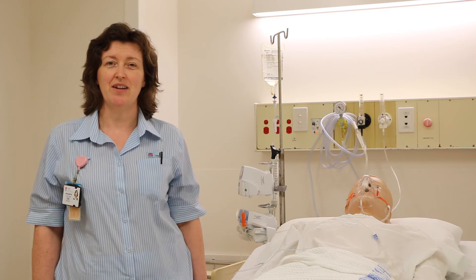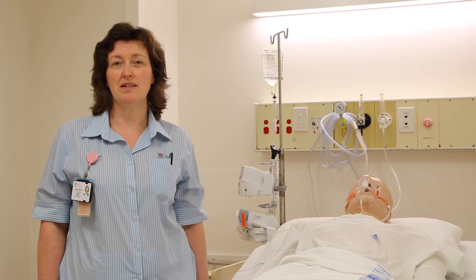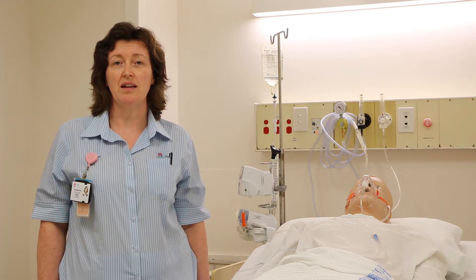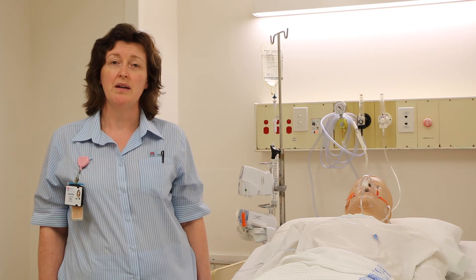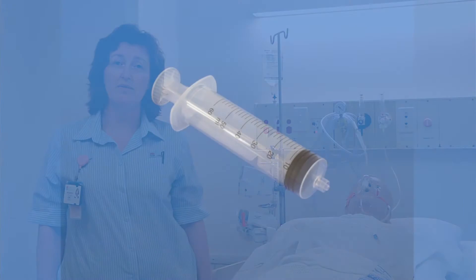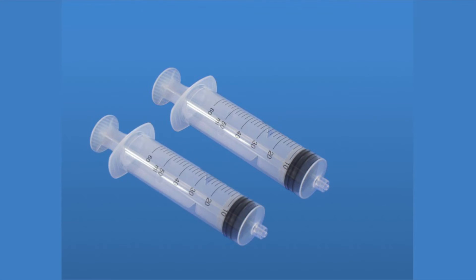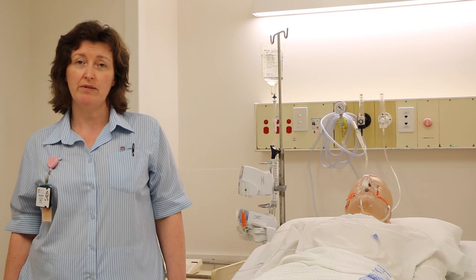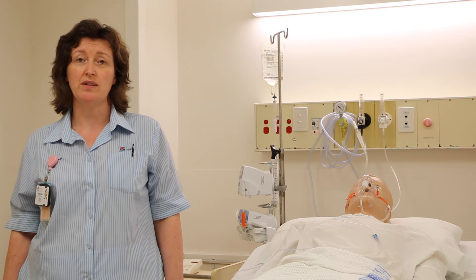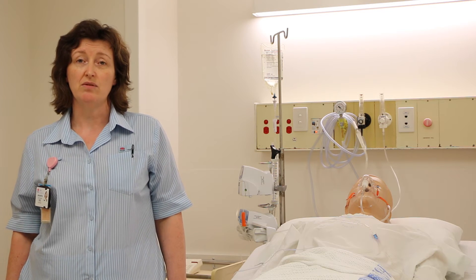18 months after the rollout of new infusion pumps across the state of New South Wales, there was an isolated clinical incident involving an infusion pump in which a full syringe of insulin was administered in 20 minutes. Within a short period of time, there were a further two incidents involving syringe driver pumps where high-risk medicines were infused within 20 minutes or less following replacement of a syringe.